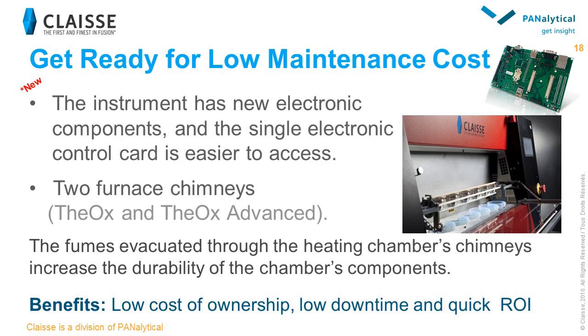Just before we finish, the TheOx Advanced features new electronic components. The multiple electronic card system with backbone has been replaced by a single electronic control card, making it easy to access and easier for maintenance. The TheOx Advanced is also equipped with two chimneys at the top of the furnace. These chimneys allow the evacuation of fumes outside the heating chamber, thus increasing the durability of the heating chamber components.